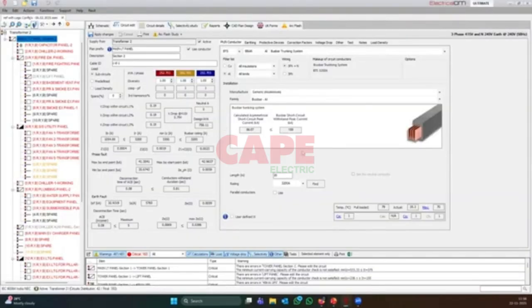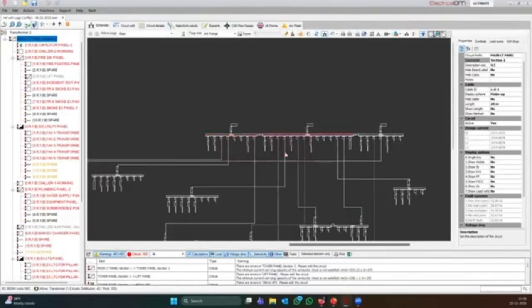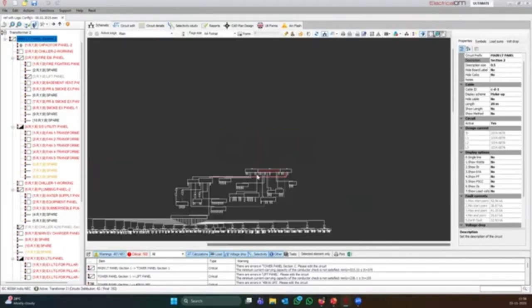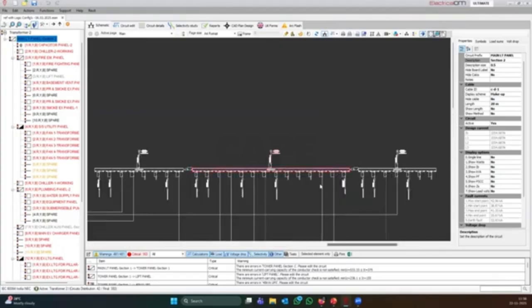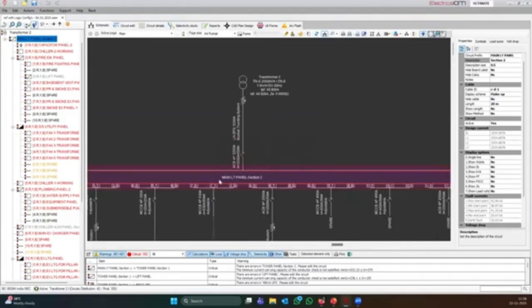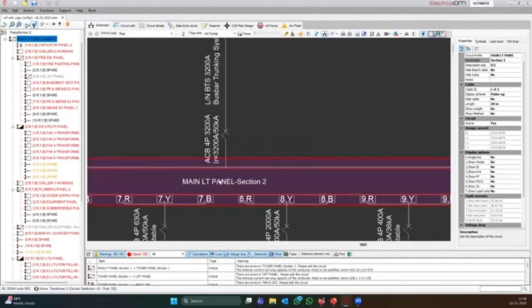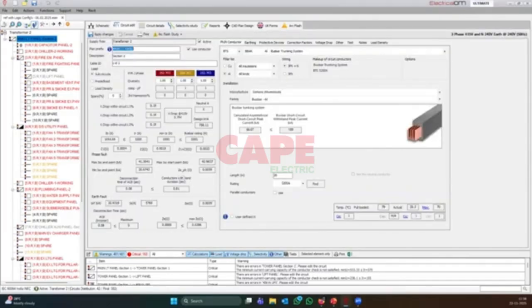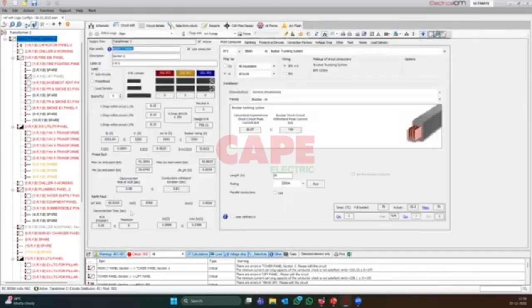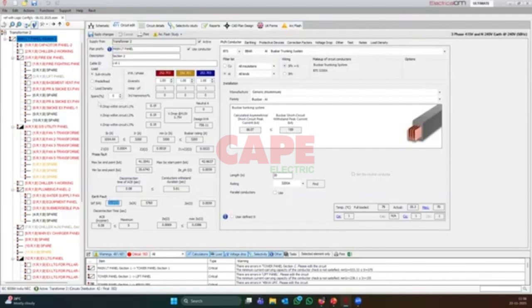Okay, so this is the residential tower. I'm not going to show about the tower or what client or all those things are. I have removed all those details. So here, if you come to the main panel section and double click it, it will show a fault current of something around 42 kiloamps, or for earth fault current, 32 kiloamps. But the major thing is this earth fault current at this location can be 32 kiloamps.